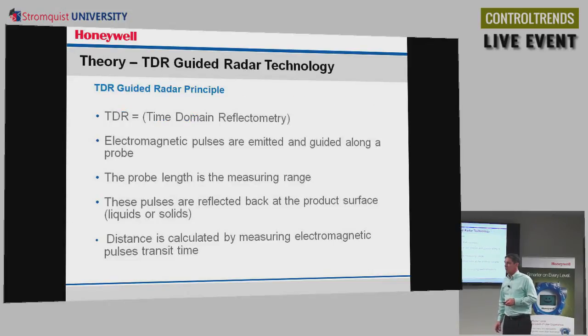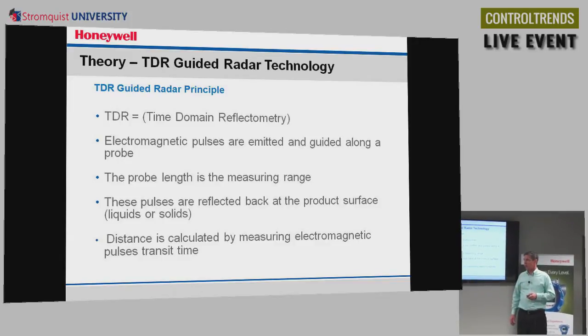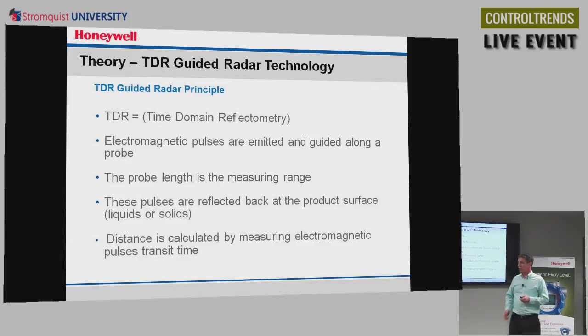So let's talk about TDR as a review. This is time domain reflectometry, the principle that we use for guided wave radar, and we're going to be talking about guided wave radar now in its applications. So we said before that we're going to generate these electromagnetic pulses. They're going to be sent down a waveguide. They're going to bounce off a surface and come back. We measure the time it takes to go there and back and get a distance from it. And whatever the probe length is, that's the measurement range.